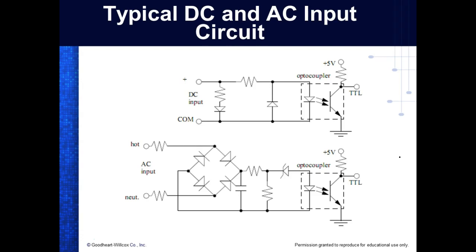So we come over here, we add resistance, so my input device doesn't have to provide a lot of current. We protect our Zener. We turn on lights, we flash lights with our input. This is transferred inside the PLC. I've got an idiot that comes out here and puts 1,000 volts out there. It blows this optical coupler, but it doesn't blow my PLC. If I've got a spare input port, now what can I do? I can move it over. You'd have to redo your program. If I let that come directly in and somebody screws up out there, they're going to blow my PLC. So every one of our inputs is isolated by what we call an optical coupler.